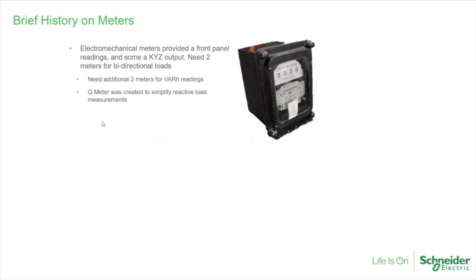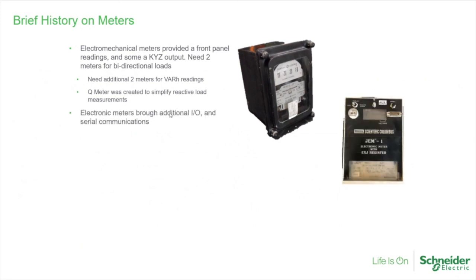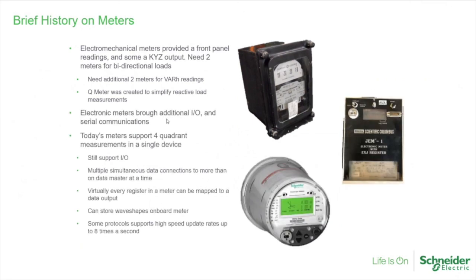A Q meter was used to simplify reactive load measurements, because you could use a kilowatt-hour meter with, I think it was a 60-degree phase former, to get Q, and that would be for the delivered real power quadrant, whereas var-hours delivered and received requires a 90-degree phase former on an electromechanical meter to capture your vars. Then we went into electronic meters, which brought additional I/O, and some of them had serial communications. And today's meters support four-quadrant measurements in a single device.